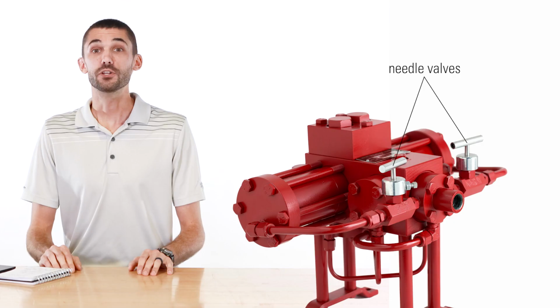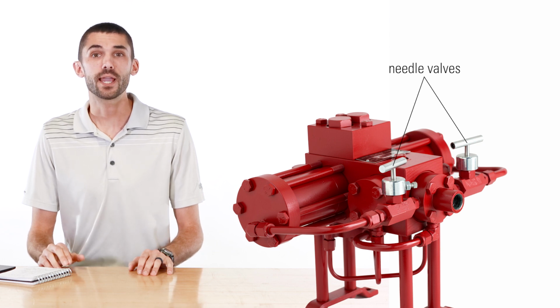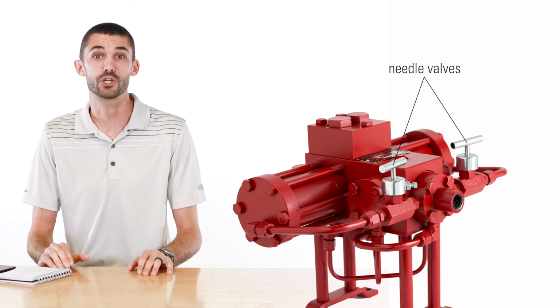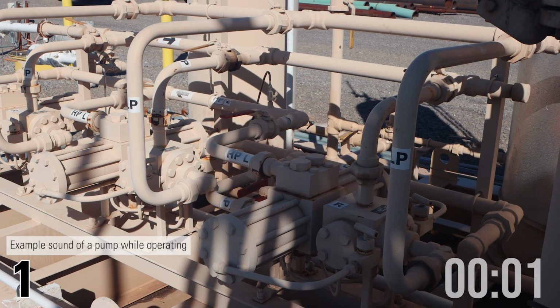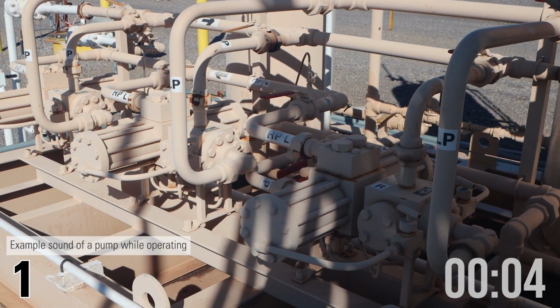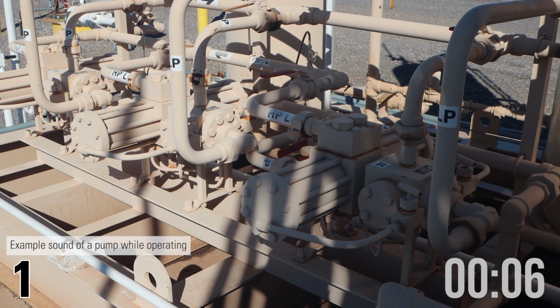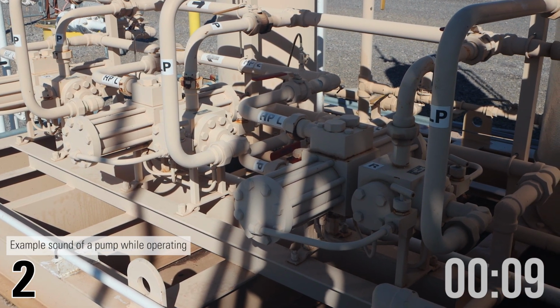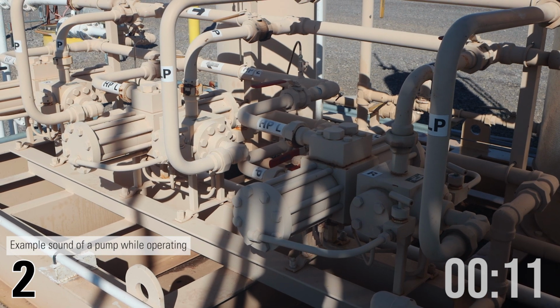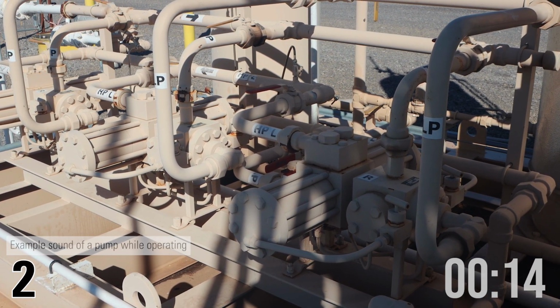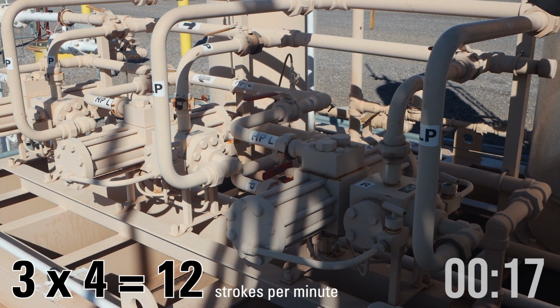Now that you have this number, you can change your pump speed to match your conditions and dry your gas sufficiently. To do this, adjust your needle valves equally, counting the strokes per minute to verify the correct change has been made. Your glycol flow rate should be checked on a regular basis to prevent both over-circulation and under-circulation.